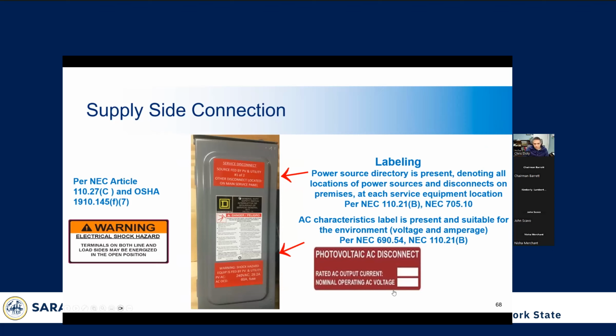All right, so here you can see some of the labeling requirements for this type of connection. You have the traditional electrical shock hazard labeling, and the PV AC disconnect as well. This would probably be for a backfeed breaker inside the panel. So you want to ensure that people know that the PV AC disconnect is there. And of note is that the PV part of the code probably has the heaviest requirements for labeling that there is. So it's kind of difficult to get right, but it's all important to maintain safety of the system. So you definitely want to familiarize yourself with that part of the code.